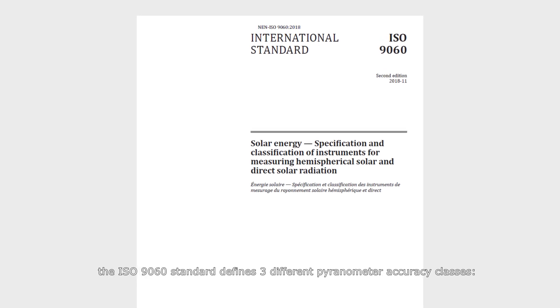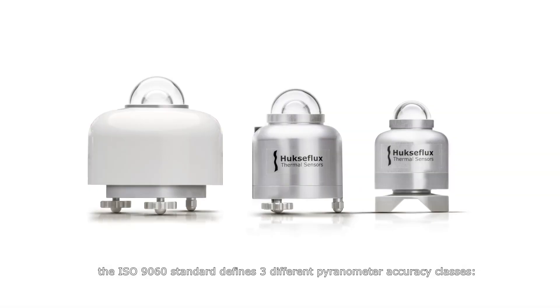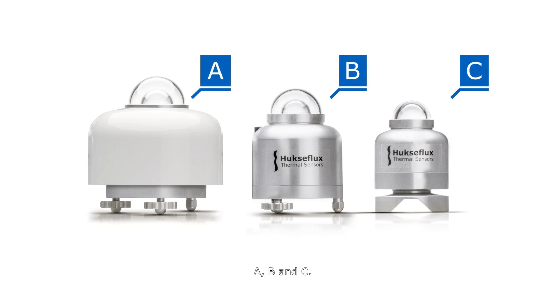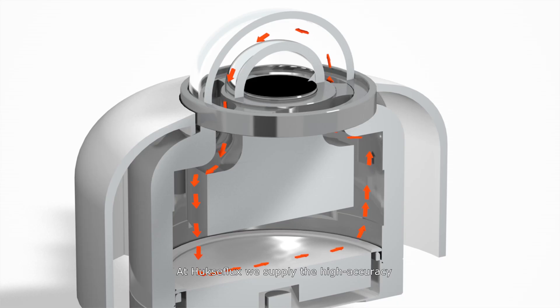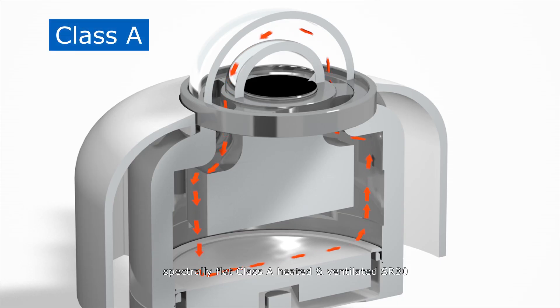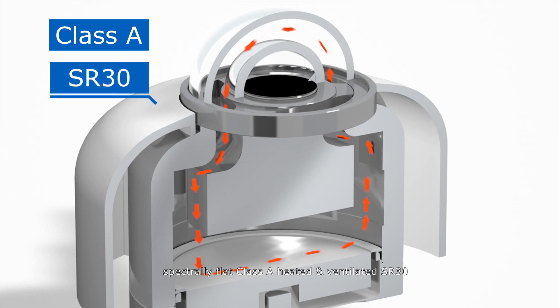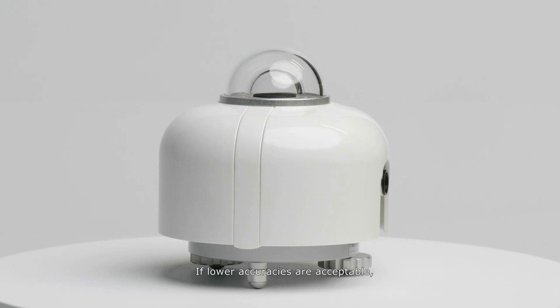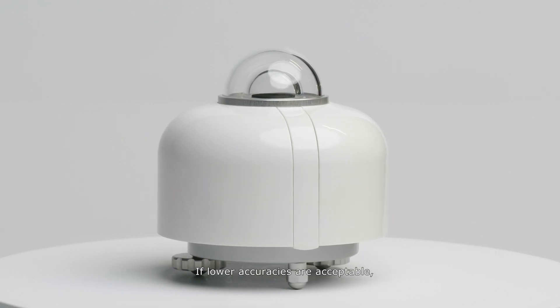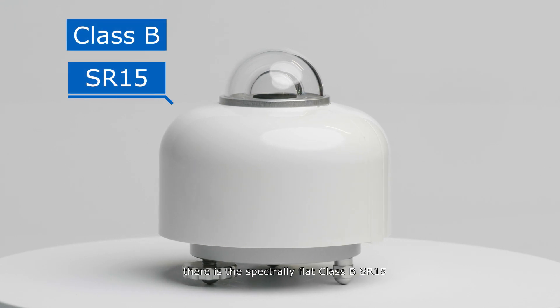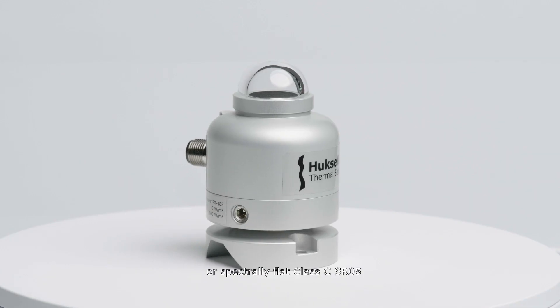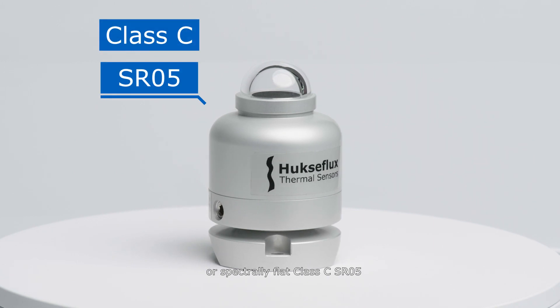To facilitate the choice of instruments, the ISO 9060 standard defines three different pyranometer accuracy classes: A, B, and C. At Hukseflux, we supply the high accuracy spectrally flat class A heated and ventilated SR30. If lower accuracies are acceptable, there is the spectrally flat class B SR15 or spectrally flat class C SR05.